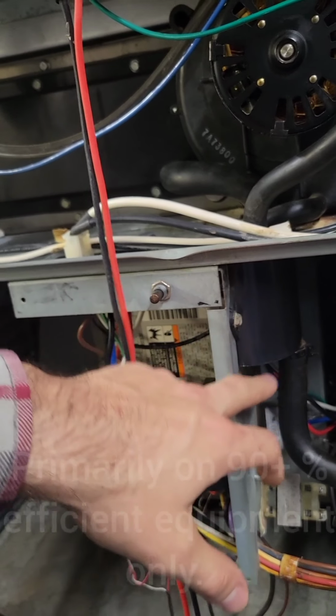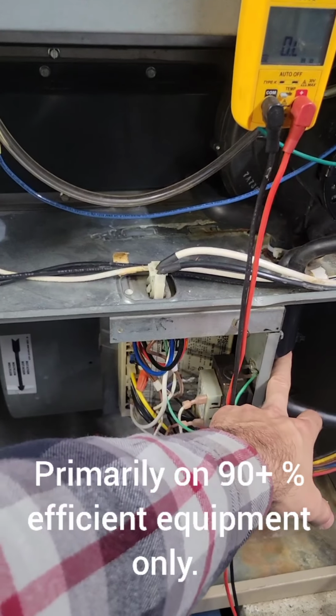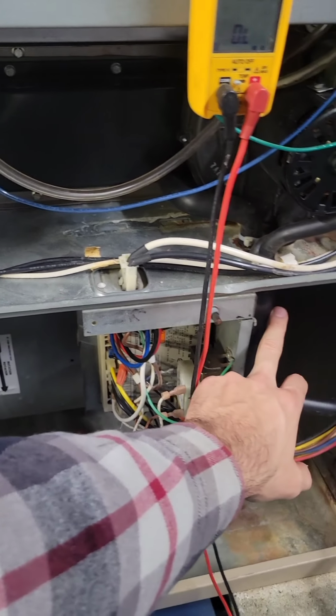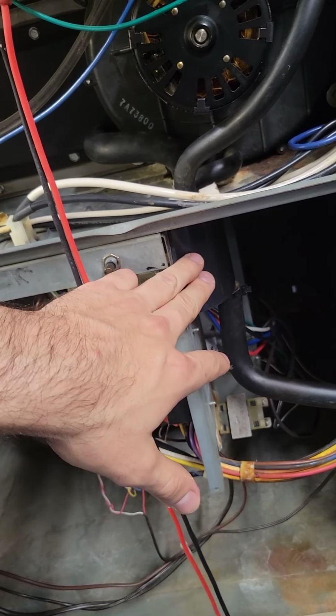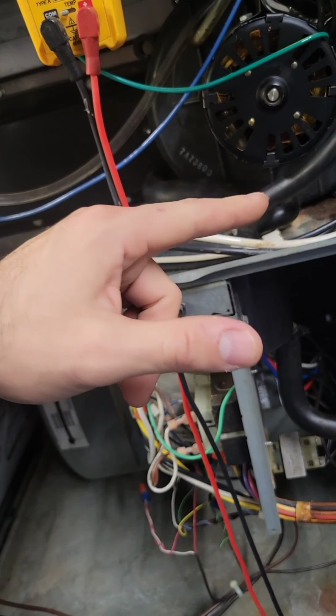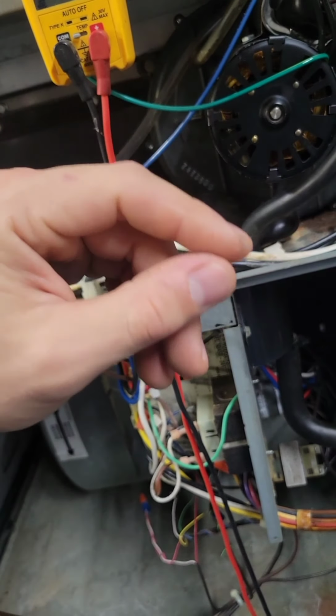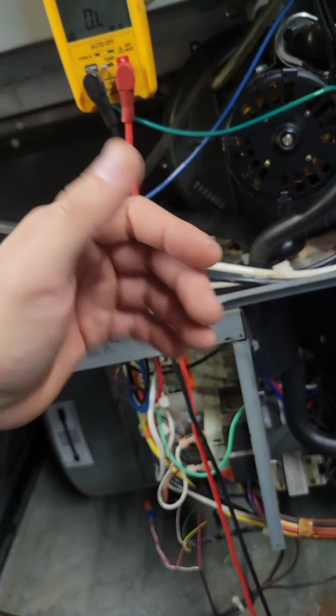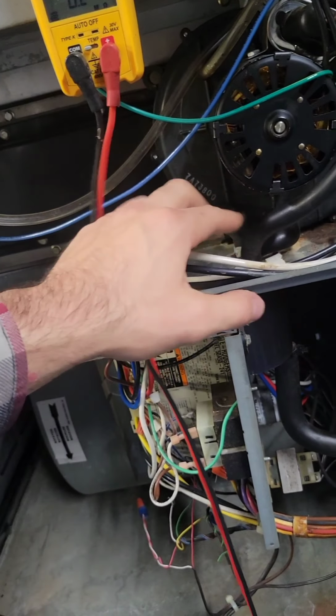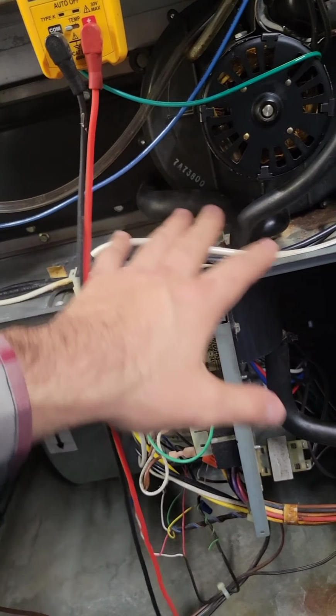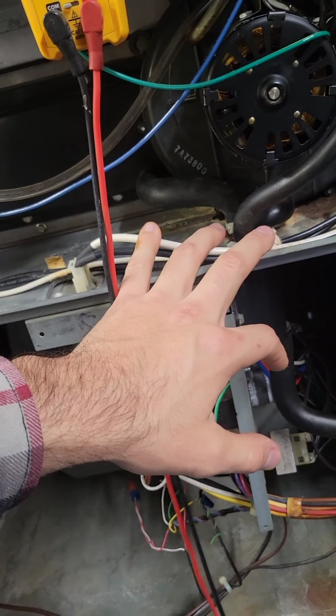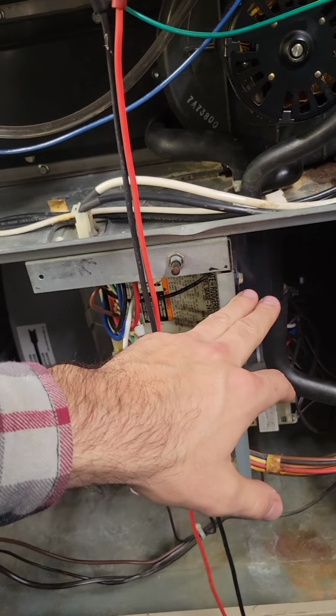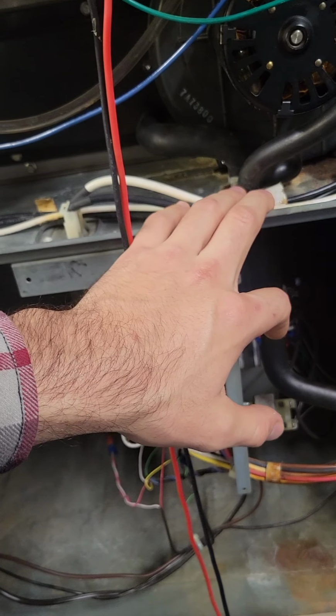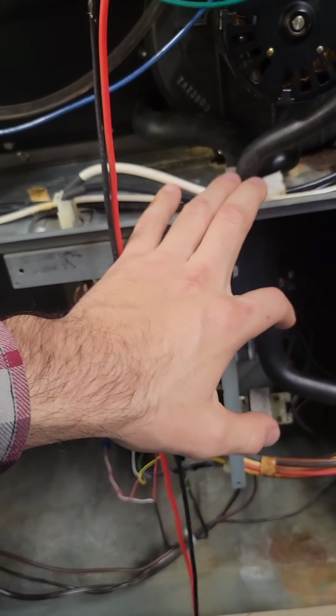So this is the trap that is created so that the condensate can drain properly, and that needs to be cleaned out as well. The reason we want a trap is that there's exhaust being produced through here, right? Through the fuel burning process, we get condensate, but we don't want any of this condensation to escape into the space, so we don't just let it go down to the pump, which he has right there. We need a condensate trap to allow the condensation to drain. That pump has been changed once before. Yeah, it's been changed before.